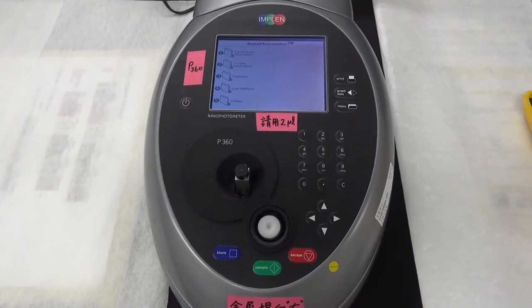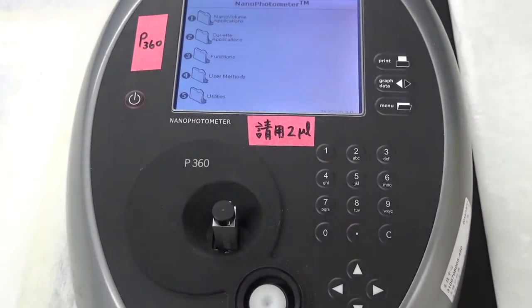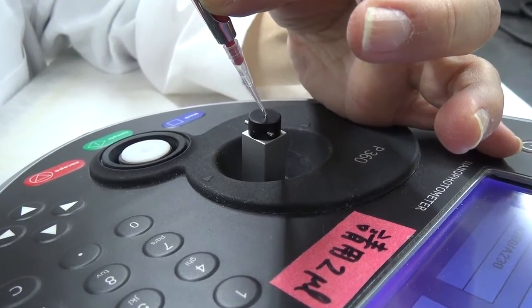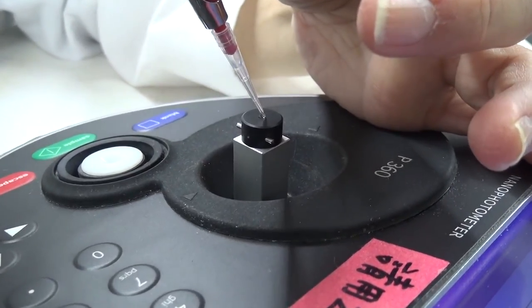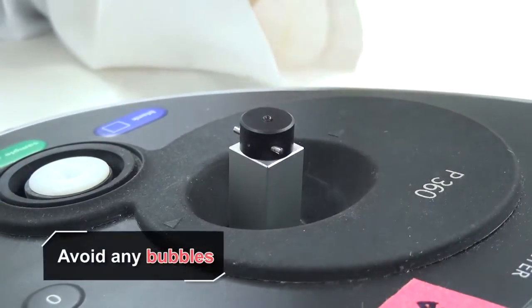5. Determine the sample volume to fit the size of cuvette. We use 2 microliter here as an example. 6. Pipet 2 microliter distilled water or blank solution into the sample well at the top of the cuvette. Avoid any bubbles.